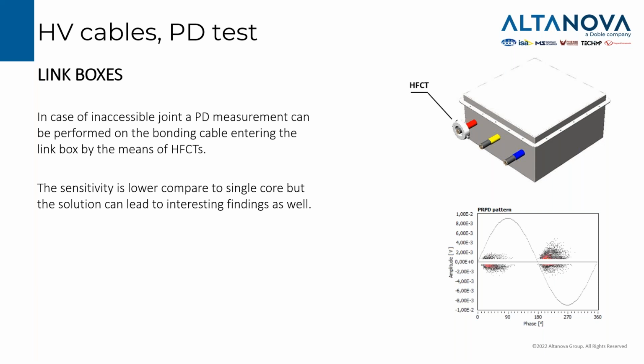By placing an HFCT on the bonding cable directly, we have a lower sensitivity, but we can pick up a signal anyway, so it can be very useful for a screening to be sure that there is something, or there is a PD, or just a signal to noise, or just background noise. It's always possible to do that. We only need to access the pit where the link box is placed.